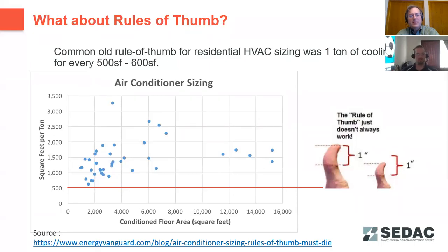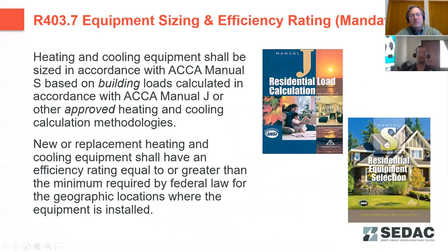You can see here, this came from a blog post from energyvanguard.com. It does a lot of posts about residential construction and energy efficiency. They actually did testing on their houses to see how closely they aligned with this rule of thumb. That red line at the bottom is the rule of thumb requirement, 500 square feet per ton of cooling. And you can see everything is beyond that, and most of them are well beyond it, almost twice or higher. So it's very important to do proper load sizing calculations for your equipment.